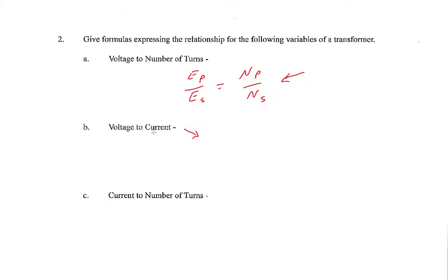On the high side, you'll have a large bushing and a small wire goes to that bushing. That's because it doesn't take a lot of current to transmit a certain amount of power on the high voltage side. And then if you look at the low voltage side, they're going to be heavier bushings and larger wires coming off of that secondary bushing if it's a step down transformer, say 120/240 secondary on a transformer. You're going to have heavy wire or cable coming off of that transformer because the current's going to be large.